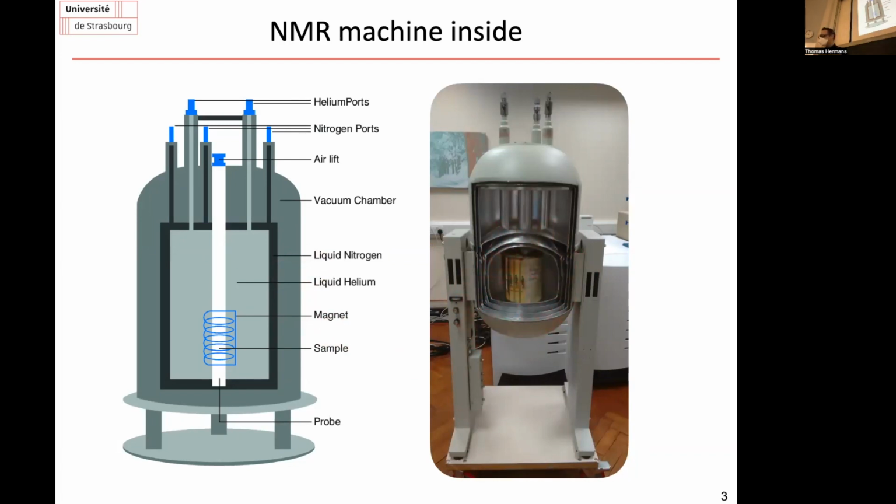Which is actually quite interesting. So the coil of the magnet is wound by hand. So there are many, many thousands of turns you have to make on an electromagnet. It's done by hand, and there's only, I think, 2 factories in the world that can actually do it. But okay, so you have this electromagnet here, and it's a superconducting magnet. So to get superconductivity, you need to be very, very, very cold.